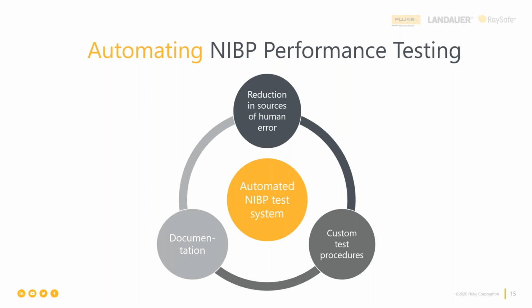Another way to do it is by being able to interoperate our test instrument with software that is a complete workflow. So not just about the NIBP portion of the test, but about everything about that medical device, because typically NIBP is not standalone anymore. It's always going to be in a device that has more than one vital sign parameter that needs to be determined and assessed. And also you have electrical safety that you need to perform as well, along with your visual inspections and any replacement of consumables that you're going to do in the process of doing your evaluation.